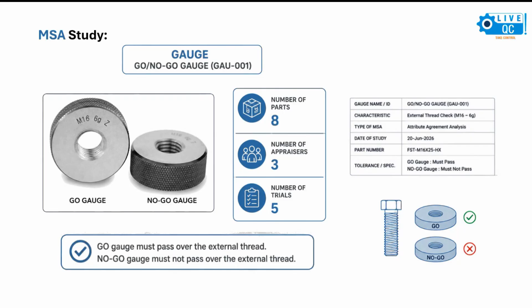And you're going to select the in-charge and all the appraisers: operator 1, operator 2, and then operator 3. They are the persons who are going to measure, and they are the appraisers who are going to conduct the study, to see whether they are reliable or not. Operator 1 gets the login, and he is going to measure each and every gauge with the 8 parts, and you enter whether it is OK or NG with a 1 or 0. After it is filled, it gets saved. Each operator gets a login, comes in there, and they each have their own privileges.